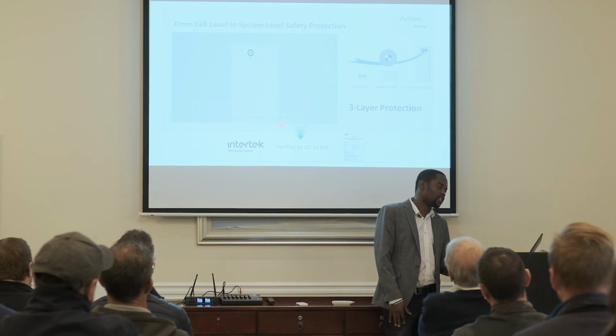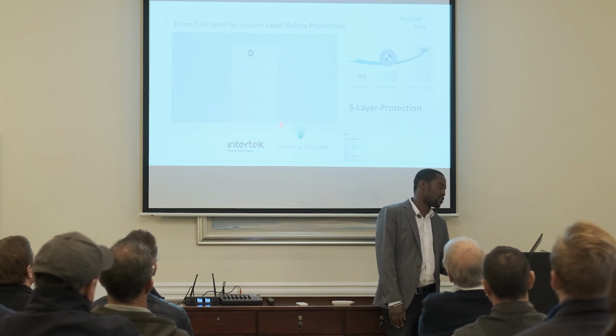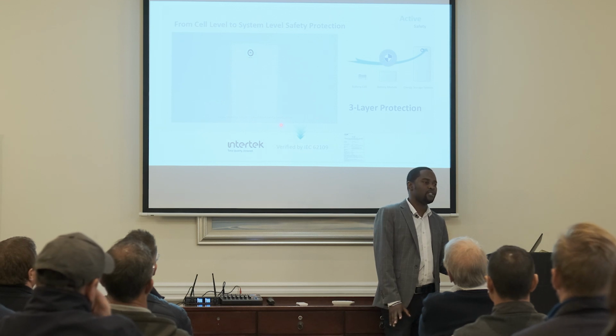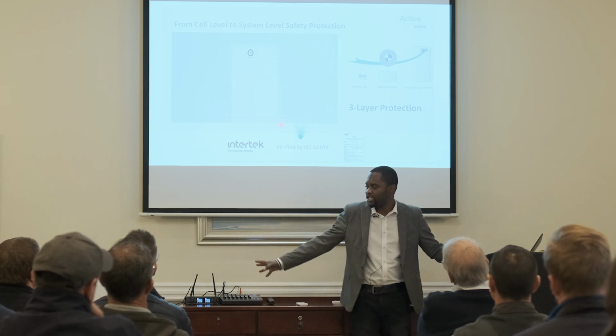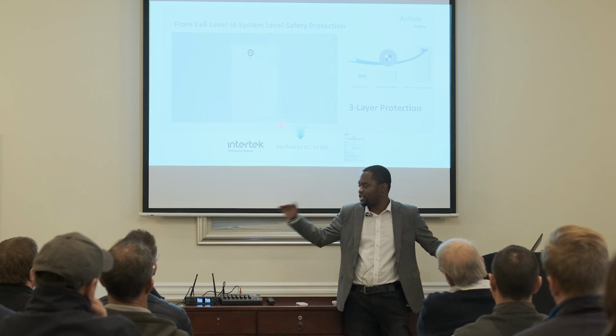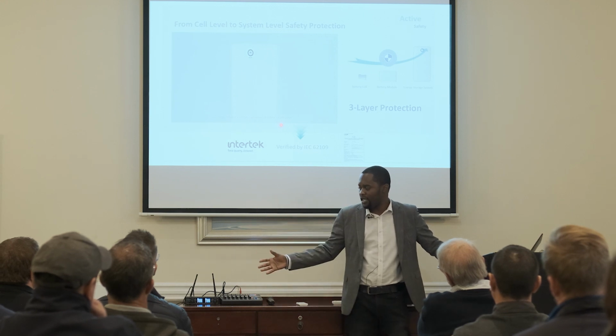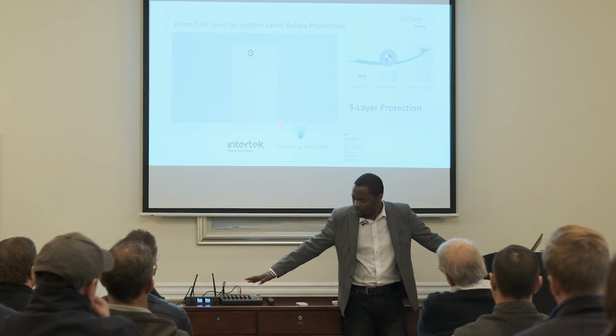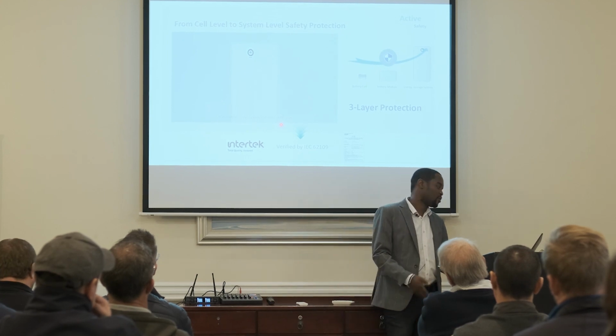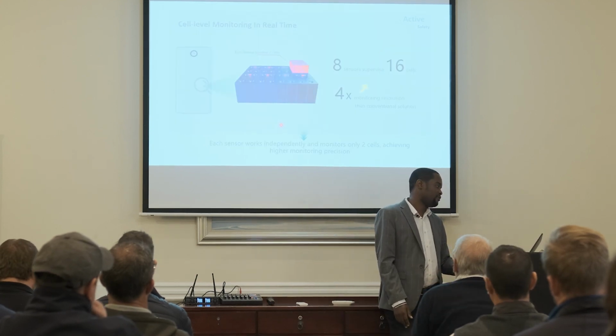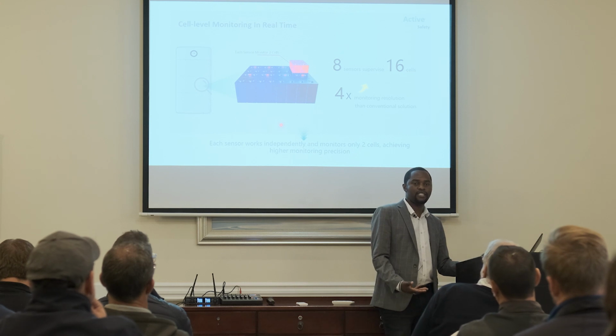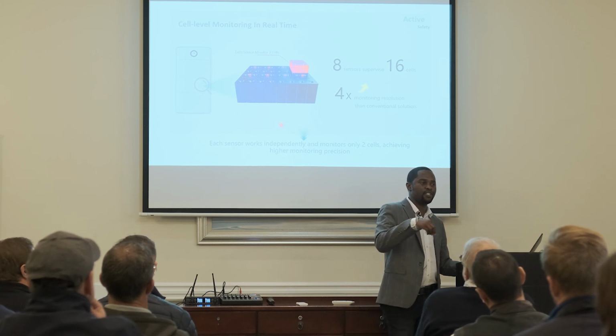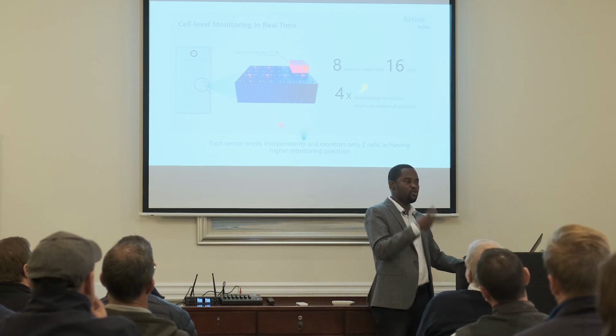Then we've got 3-layer protection, that anti-fire pack that Raf talked about. It's 3-layer because it's not only protecting you at the inverter or system level, but we've got protection at system level, which is the whole compact thing, then also at battery module level and at cell level. So this is the 3-layer protection that we have. We've got sensors that are supervising the operation of the cells. So we've got one sensor per each 2 cells.